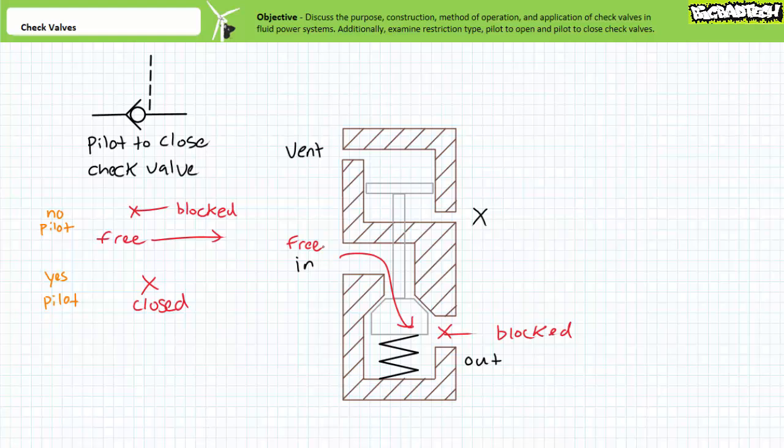Again, a pilot to close check valve acts just like a regular check valve in the absence of a pilot signal. One direction is free flow, the other direction is blocked. In the presence of a pilot signal, the check valve closes and both directions are blocked.